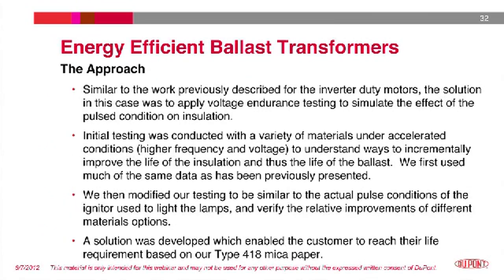For this design, we again looked at designing an insulation system which could withstand high levels of partial discharge at elevated temperatures. We worked with the ballast customer to design a voltage endurance test which was more severe than his worst case scenario from both a voltage standpoint and from a frequency standpoint. We used 360 hertz versus a normal 60 hertz operation. We then modified our testing to be similar to the actual pulse conditions of the igniter used to light the lamps and verify the relative improvements of different material options. A solution was developed which enabled the customer to reach their life requirement using an insulation barrier based on Type 418 paper, which lasted 50 times longer than their standard barrier under our testing, which enabled them to meet their life requirements for a lamp out condition.